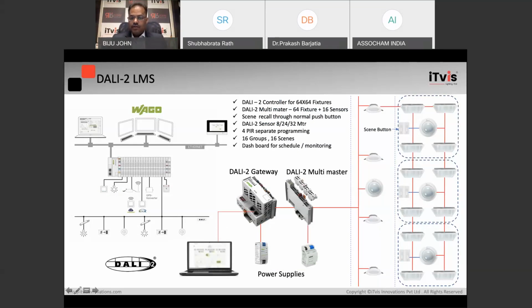What you see here is a DALI multi-master. In this automation structure, a DALI multi-master can connect 64 DALI luminaires plus 16 DALI sensors. Take the case of 3 different rooms and a passage. Let's take a floor with 3 or 30 rooms, whatever. I just took 3 rooms, and 4 2x2s in each room. You need one DALI sensor in each room, and you need DALI drivers in these luminaires. All these luminaires and sensors are connected to a controller called the DALI multi-master, which has a power supply, because that power supply goes through the bus to power up the DALI devices.